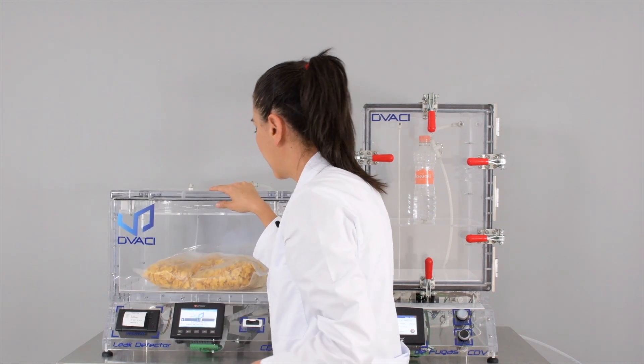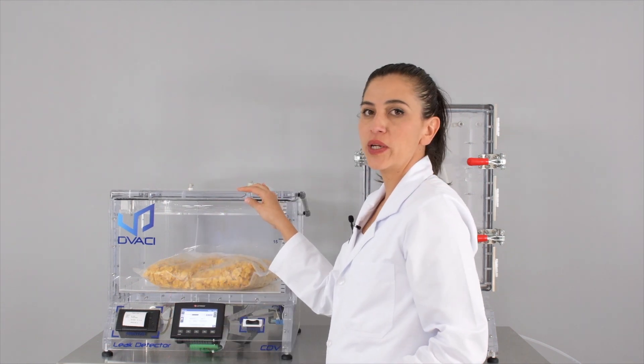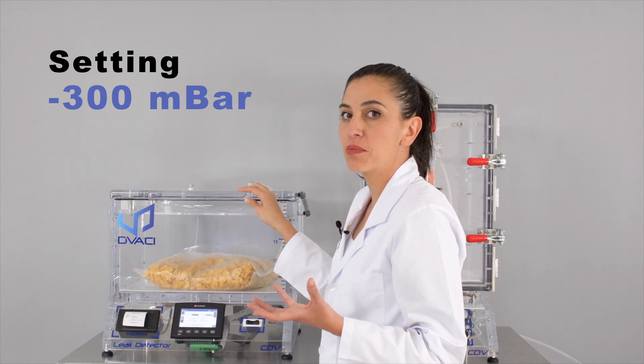In order to close this lid, the vacuum sucks it in — you don't need to use clamps. In this test we are going to simulate a difference in pressure of minus 300 mbar.